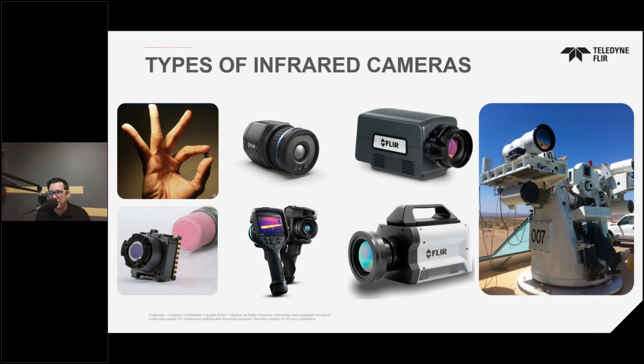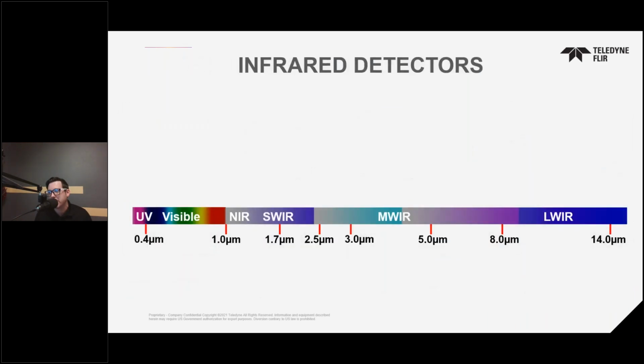In the center right of this frame, going from top to bottom, you see our cooled high definition A8580 model camera, which is available with a 1280 by 1024 resolution, and it can be had at that same resolution and frame rate options in both midwave InSb and long wave SLS material. Below that is the X series platform, bottom center, the silver camera there. That is just loaded with connectivity options and the highest frame rates, highest performance. To the far right, that's an example of our range science or RS models. These are typically used at open air test sites and other harsh environments for long range infrared captures. So it's just a very quick rundown of some common examples of camera types here.